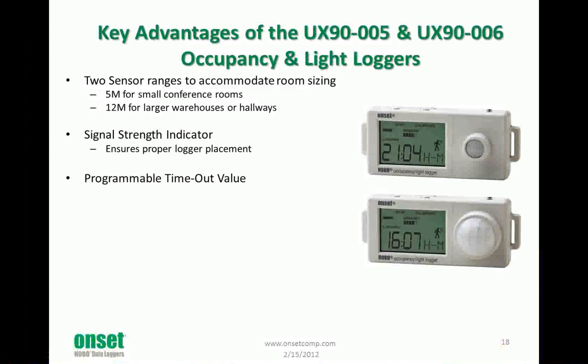The occupancy sensor has a programmable timeout value, similar to what you'll find in most occupancy switches, where you can set this from 1 second to 15 minutes. So if it's set for once a minute, and it sees movement in that minute, it resets itself. This gives a good indication of what your payback will be when you install occupancy switches based on the data.